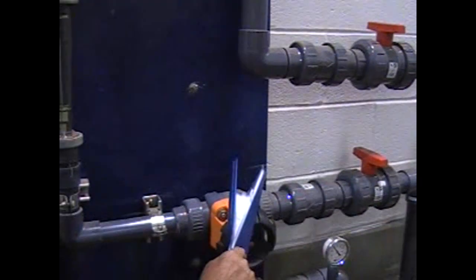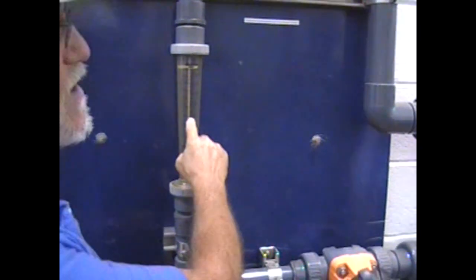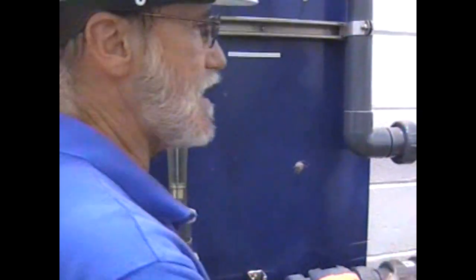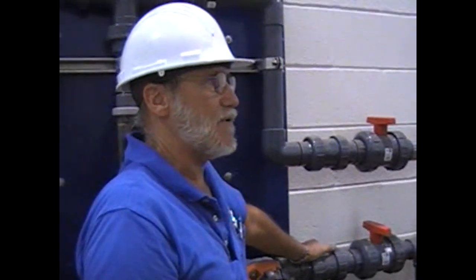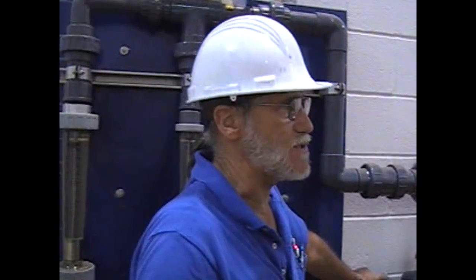Then you just come over here and throttle this guy right here. You cut down the amount of bleach. You were putting 9 gallons in, you drop it down to 8. Let it run and test it. And then once you do that, you should be good for that whole batching right there. Now you can come back in a half hour, an hour, and retest it again. There's nothing wrong with being sure and safe.